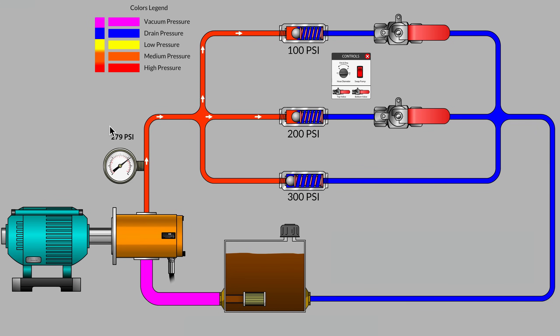Does that sound like an efficient way to get hydraulic flows to occur on more than one parallel branch? No, it does not. But it is common enough. It's not usually done by undersizing hoses or oversizing pumps. As much as flow on two parallel branches may be achieved by opening directional valves on each of these two branches only slightly. But a directional valve that is opened only slightly on this branch and only slightly on that branch is the same thing as having undersized hydraulic hoses in the simple analysis.